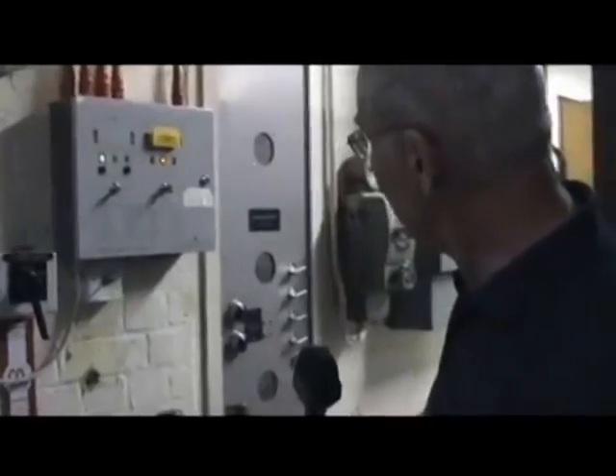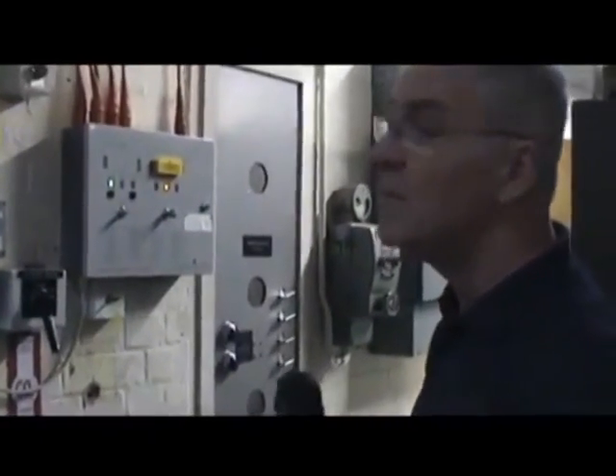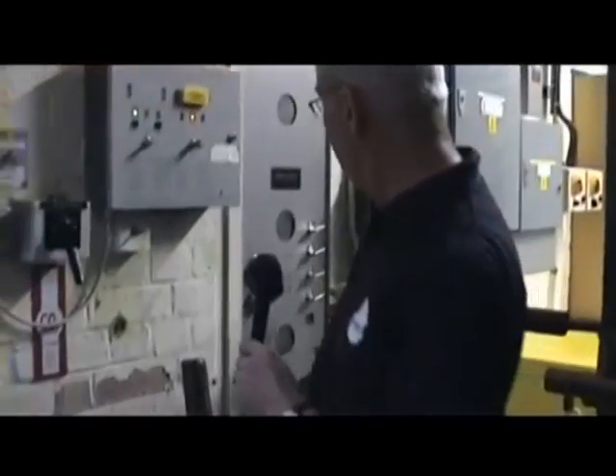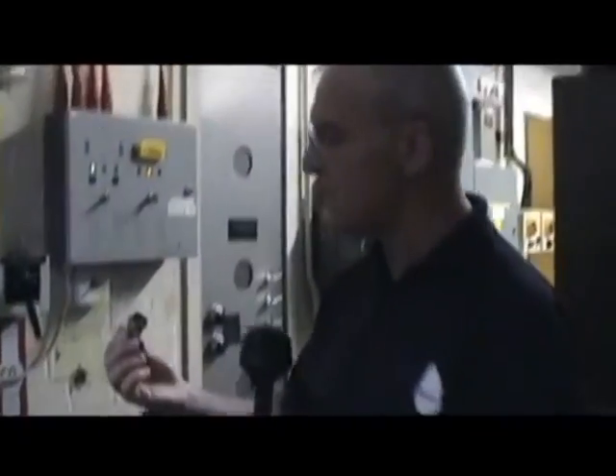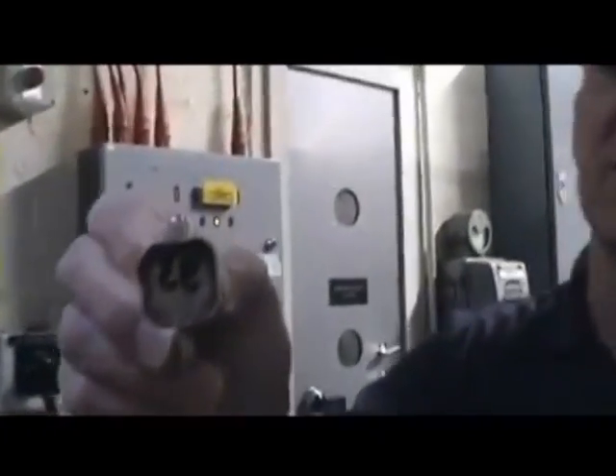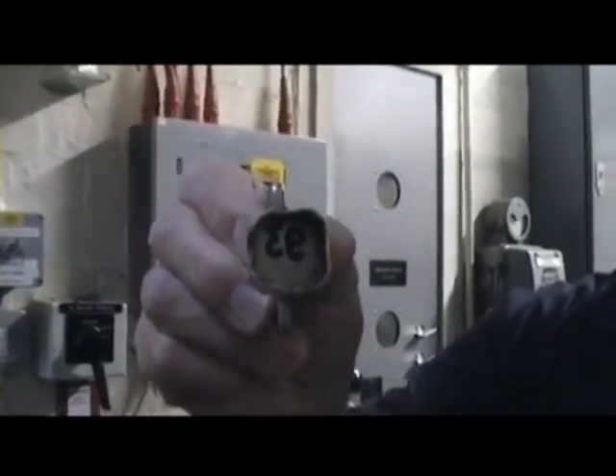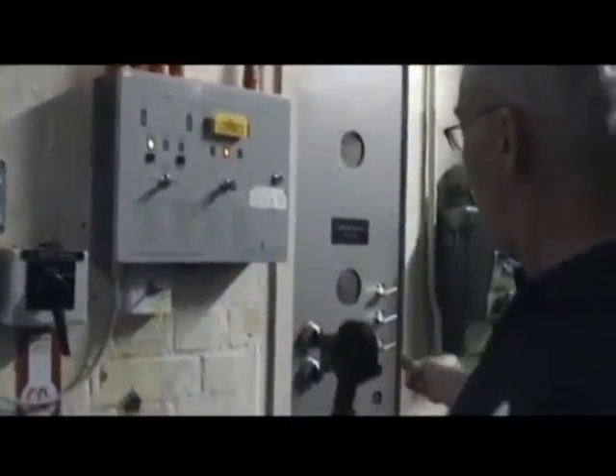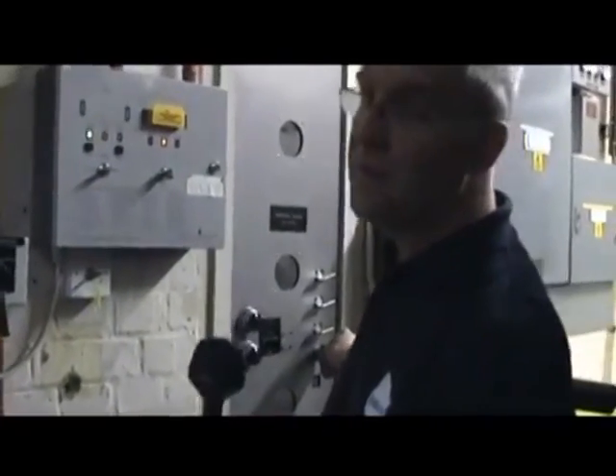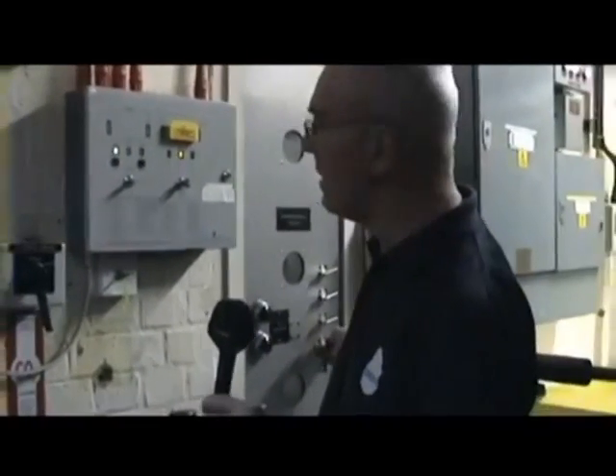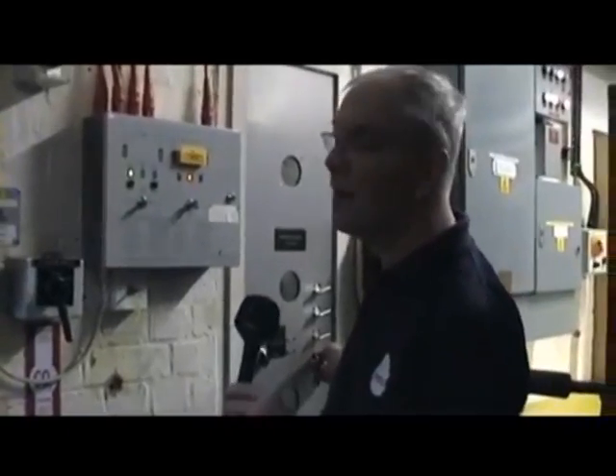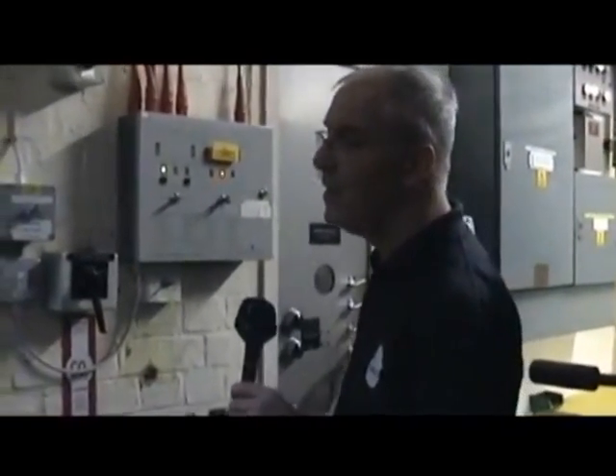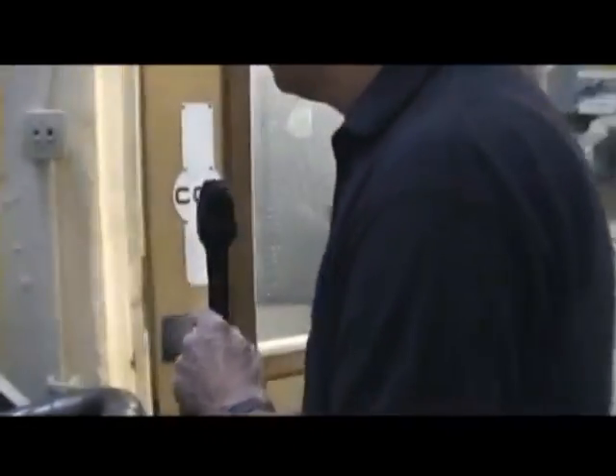In a minute, we'll go through to the modulation enclosure and see what's in there, but to get in there, we need to gain access from this panel here. At the moment it is unlocked, but we need to get one of these keys out. These are called Castell keys. This one's got a number inside. It says 93 on it, engraved inside. And it's such that when you put it in, it locks with the ident on the other side. So 93 fits with 93. You can't get 95 to go in there. I've already got a key here in the door. So we can open the door, go in through.